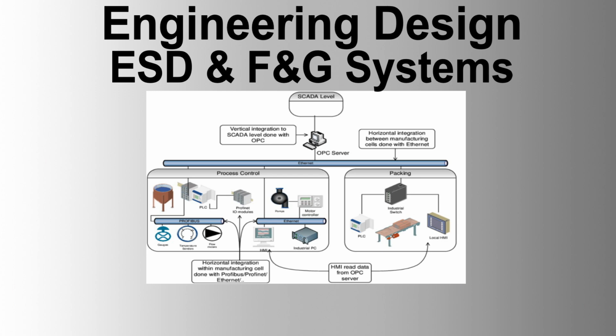ESD F&G printer. 1. Printer integration. Separate printer not required. Events integrated into the DCS and printed using the DCS system printer. Port available for an external printer if required. Operator station. 1. Station requirements. No separate operator station required for ESD F&G system. All graphics related to ESD F&G displayed on the DCS operator station.